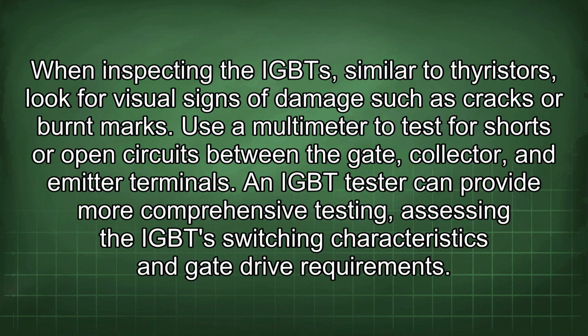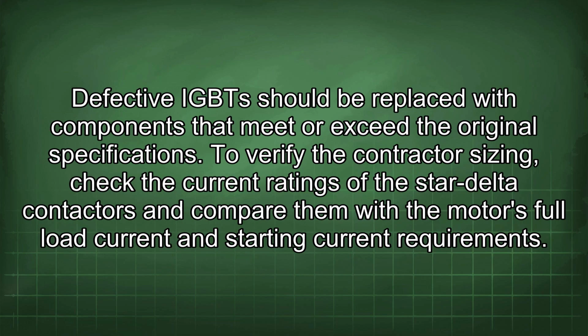When inspecting the IGBTs, similar to thyristors, look for visual signs of damage such as cracks or burnt marks. Use a multimeter to test for shorts or open circuits between the gate, collector, and emitter terminals. An IGBT tester can provide more comprehensive testing, assessing the IGBT switching characteristics and gate drive requirements. Defective IGBTs should be replaced with components that meet or exceed the original specifications.